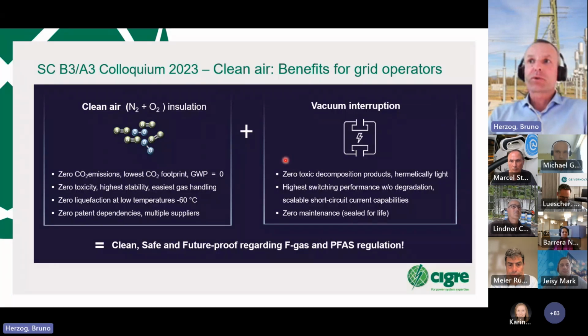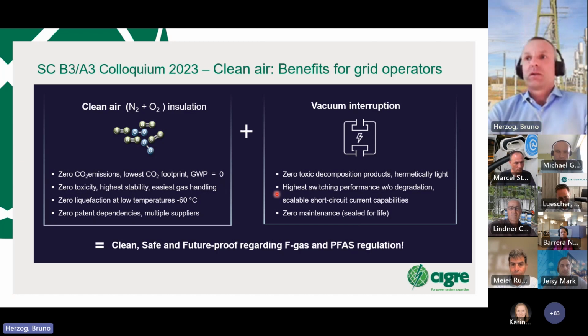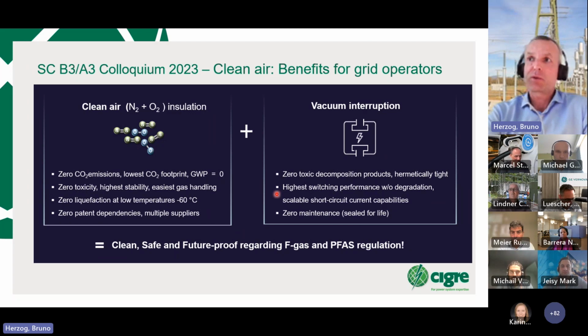We are combining vacuum technology together with clean air. For interruption, because it's closed, we have no toxicity escaping. We have really high performance vacuum interruption, known for many years from standard medium voltage as well as high current generator switchgear, for example, so we have long experience in this capability. And it's sealed for life - vacuum only works if it's really closed; otherwise we have a problem.